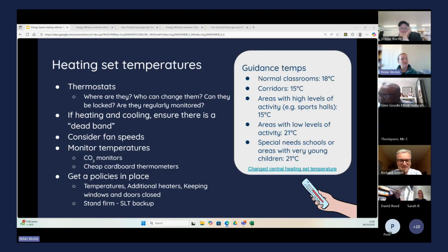Richard mentioned fan speeds as well. If you have air handling units, make sure they're not blowing too hard, because even warm air blowing fast will feel cooler. There was a school I spoke to recently in Bristol where all the thermostats were set to 23 or 24 degrees and it still felt cold - almost certainly because the air was blowing too fast.